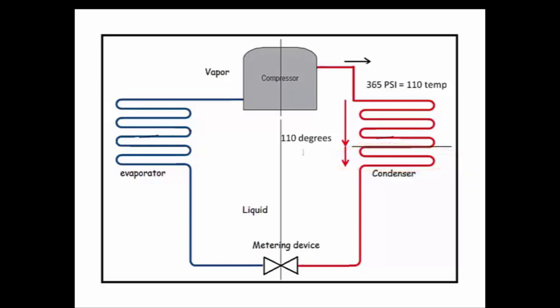Having the proper amount of liquid stacked up in the bottom of the condenser is critical, because as the load increases on the air conditioning system, the amount of liquid required in the evaporator increases. The liquid stored in the condenser supplies the increase in liquid needed for the evaporator to operate properly and prevents the condenser from running out of liquid refrigerant at high load conditions.